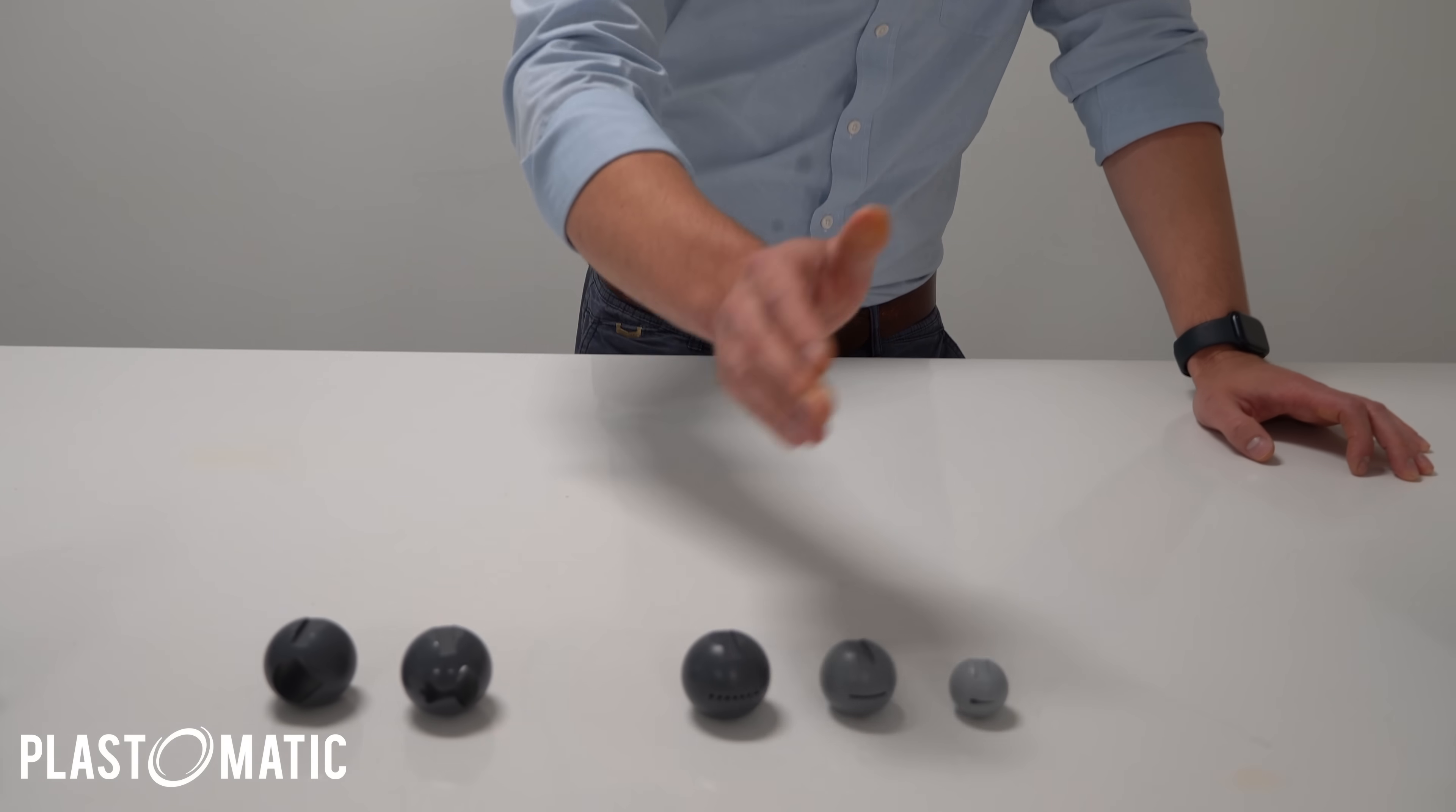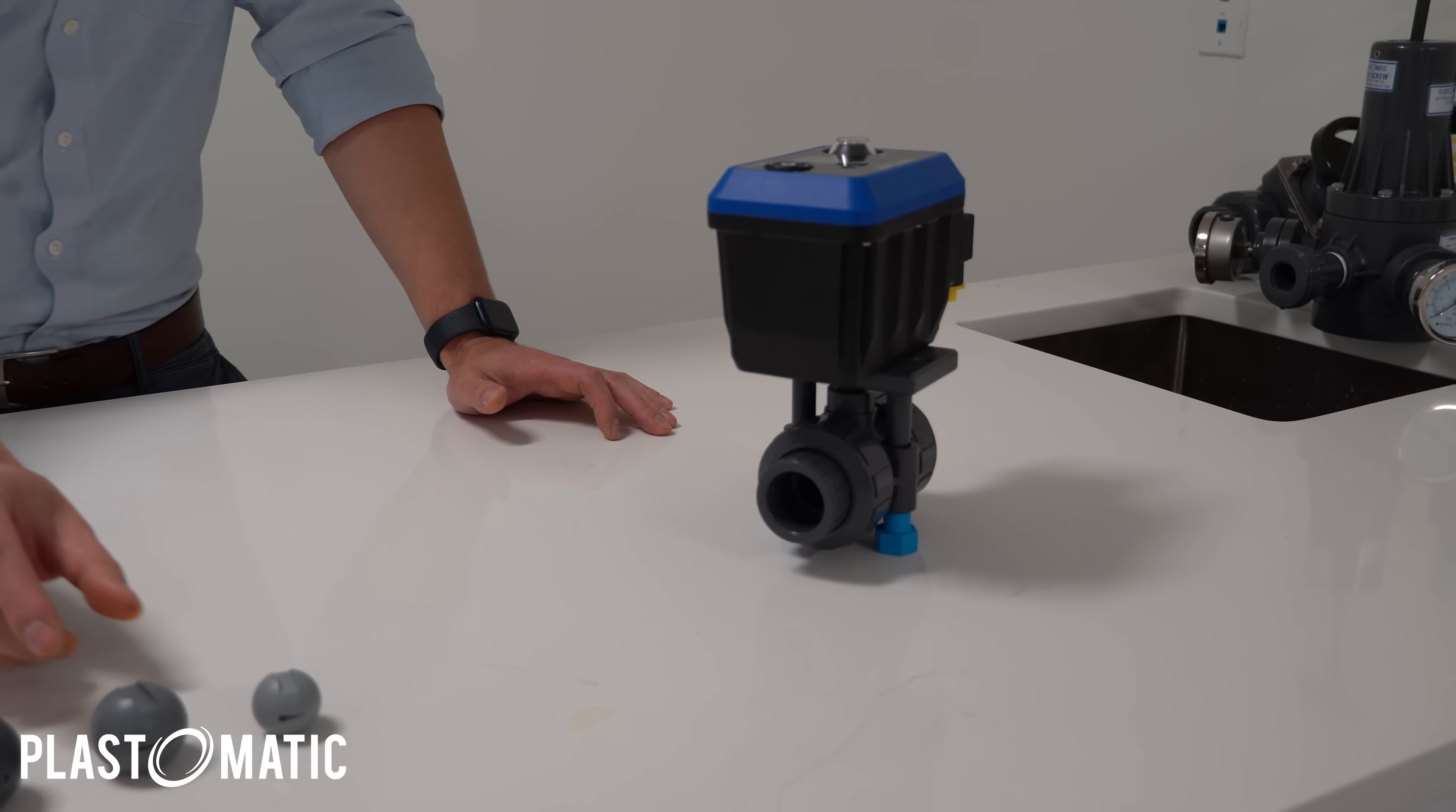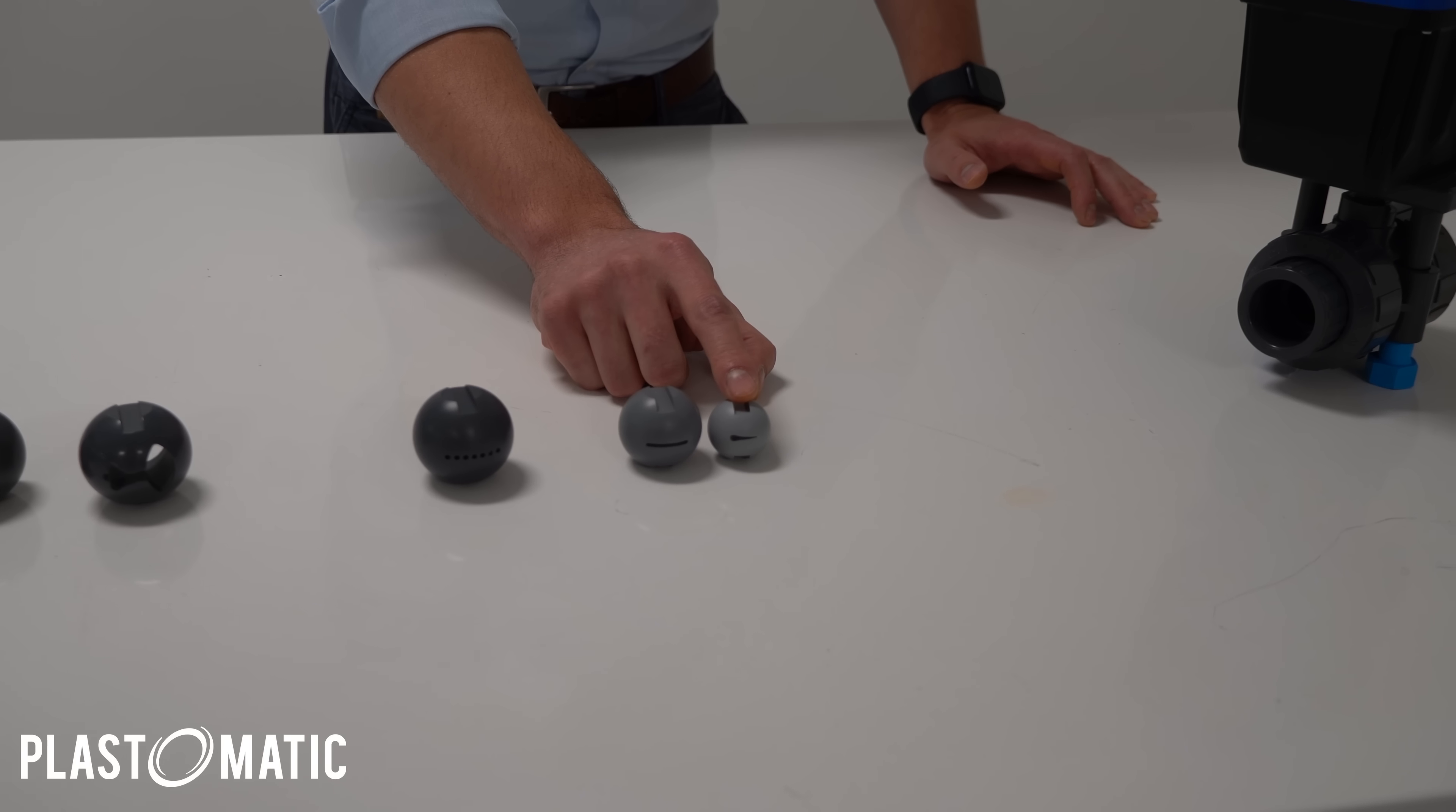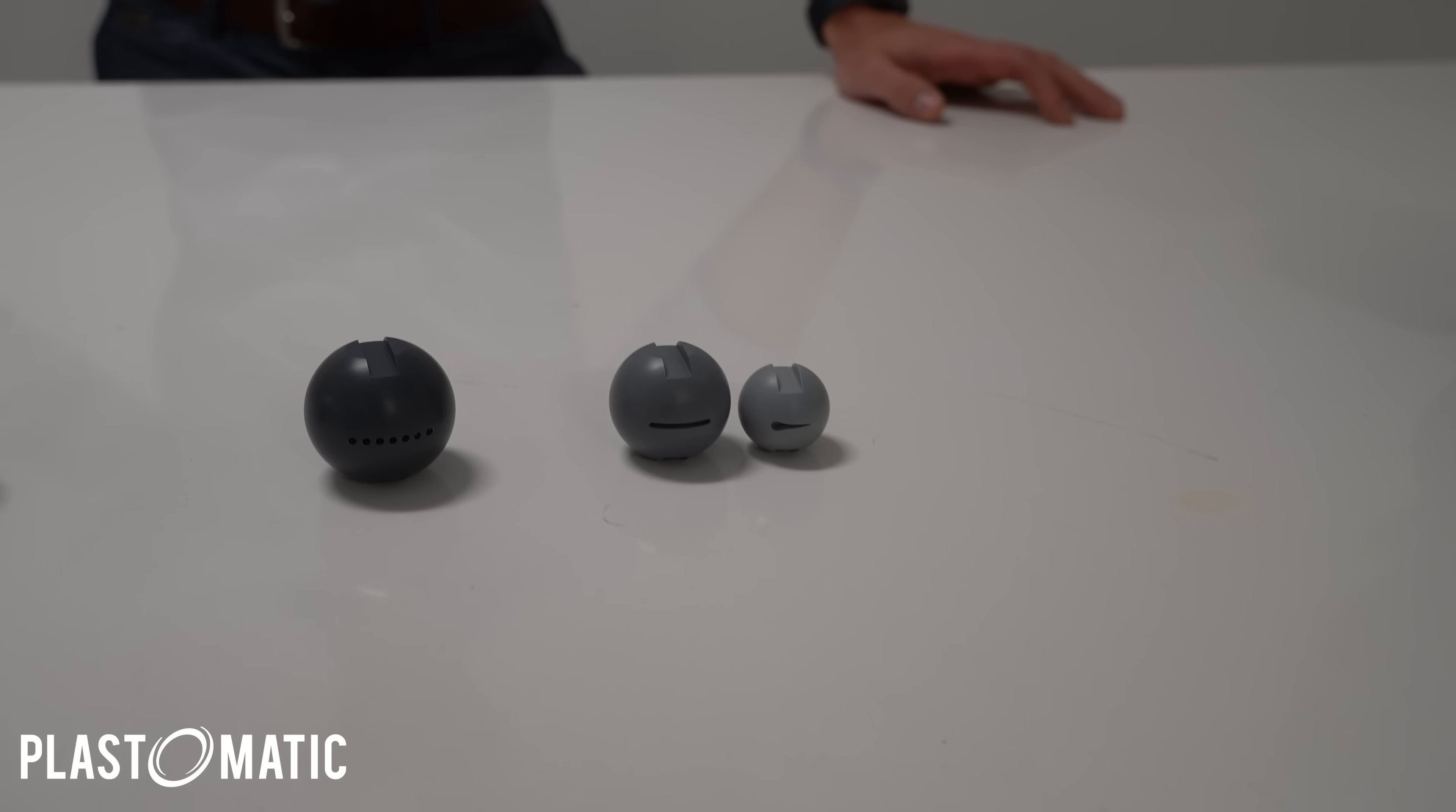With a ball like this, with these holes, you will get an interruption and your electric actuator will not be able to pick up in between those points. You essentially have dead zone. So we are able to, using precision machining, dial in a slot that will allow uninterrupted flow that will be characterized according to the customer's flow curve that's requested.